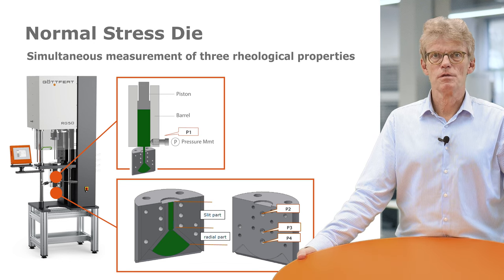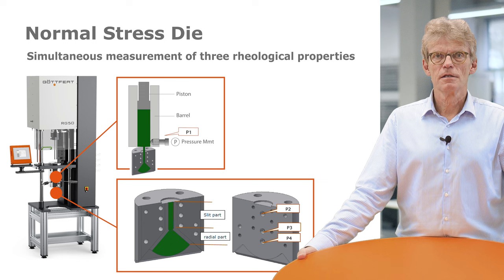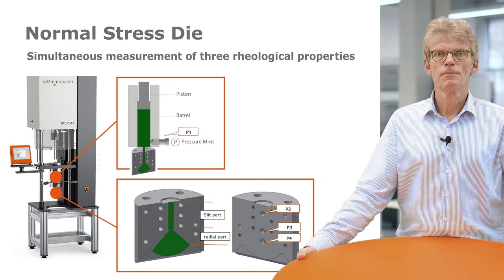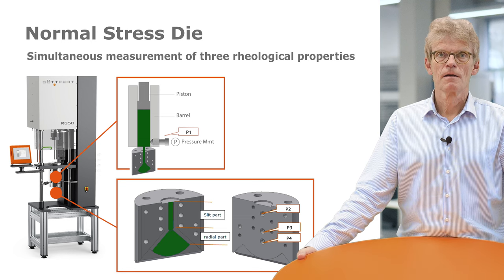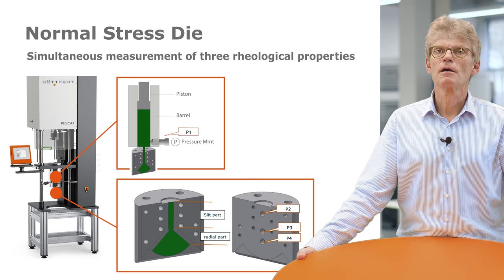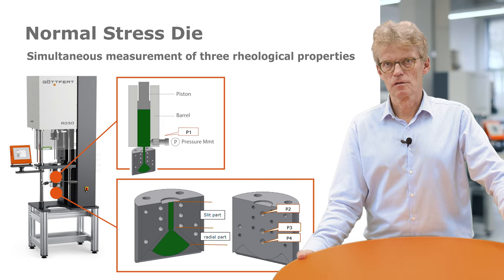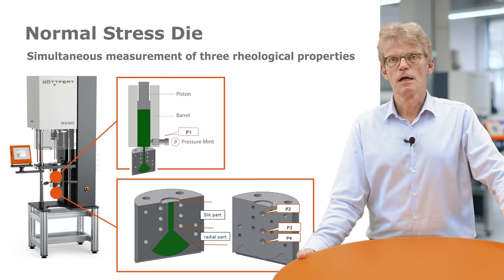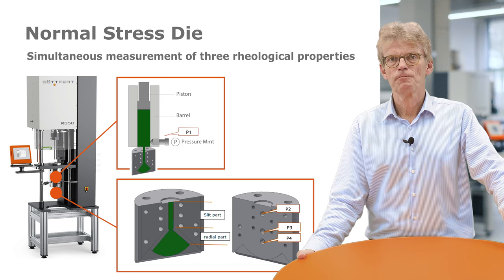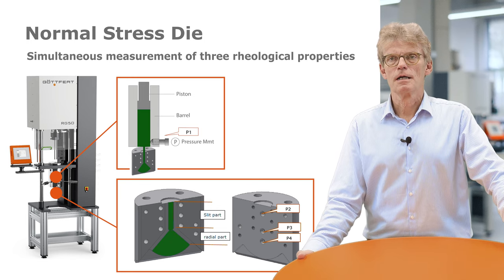The pressure is measured in the barrel of the capillary rheometer or the on-line rheometer, here named as P1. In the slit die, we have two pressure transducers, P2 and P3, which allow us to measure shear viscosity. From P1, from the entrance in the barrel to P2, we get the entrance pressure loss and measure elongation viscosity. In the radial part, we have another transducer, P4, and from the pressure difference P3 and P4, we get the first normal stress difference.